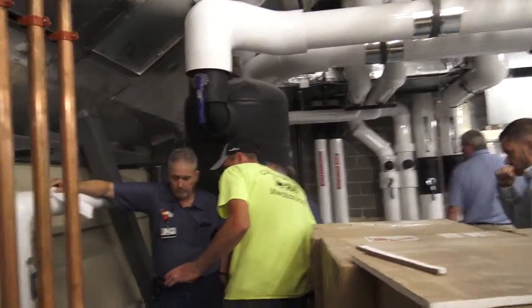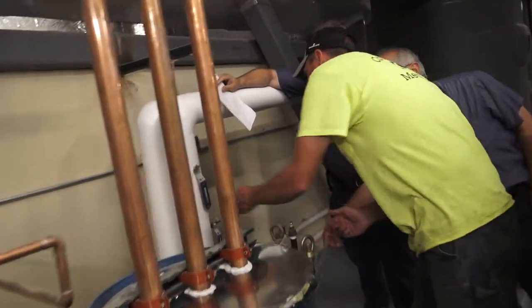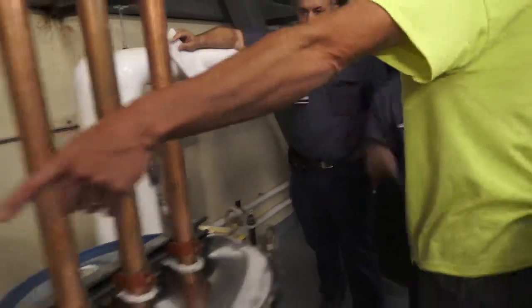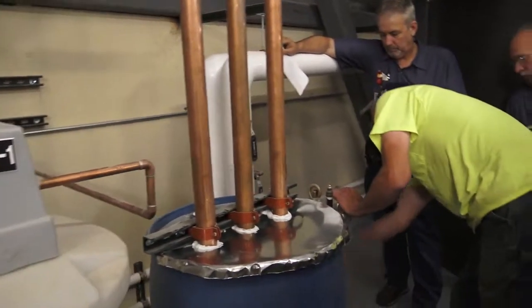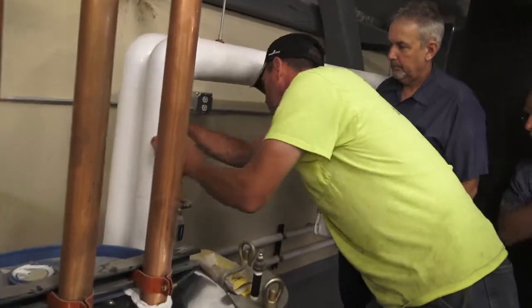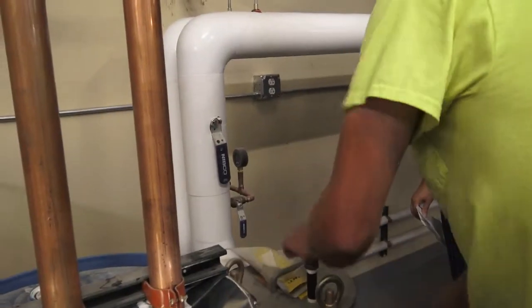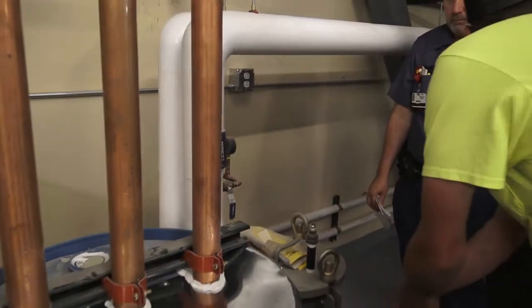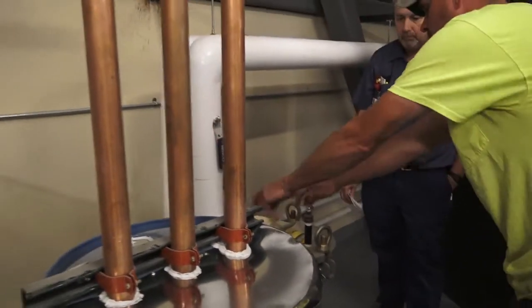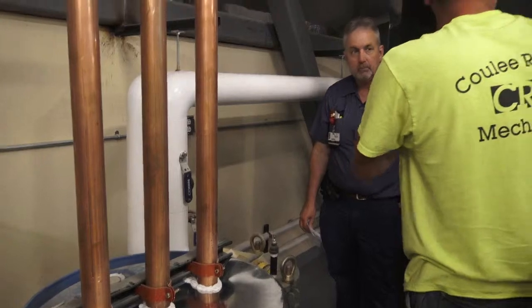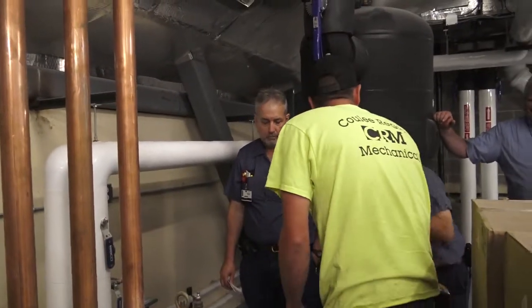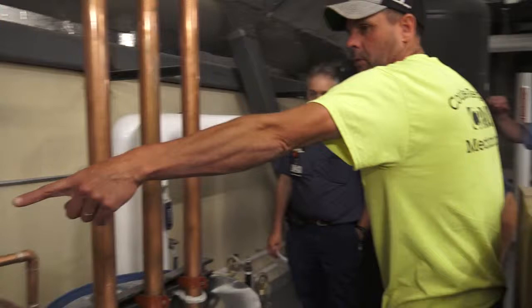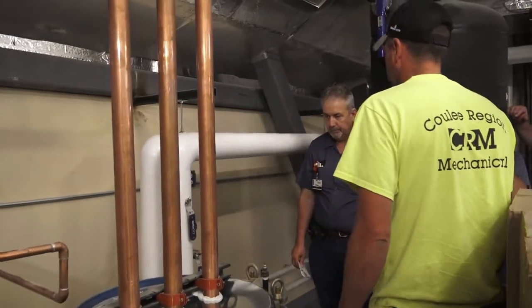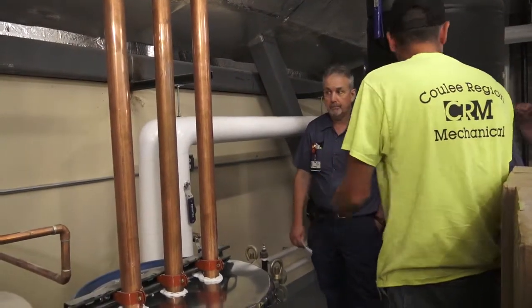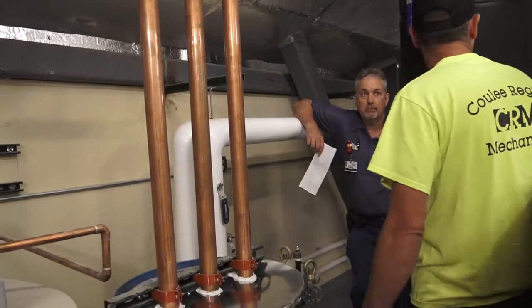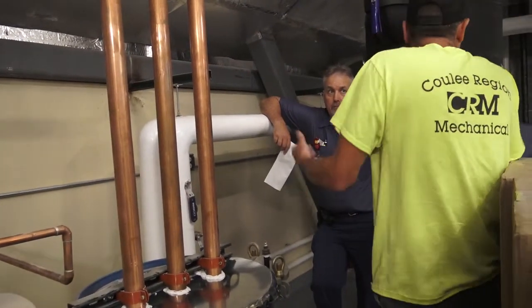But otherwise, the valves over here, once you shut this down, you bleed it off. That excess, do we just pour it back in? Yep, just undo that, take your hoses, shut where the valves are. There's a valve there, a bleeder, open it up, take a bucket and drop it in there. And you take that off and leave them off, they're just cartridges, that's all they are, shorter than the ones over here. Then just take that excess and dump it right back in there, and you're good to go. If you've got any problems with glycol, or if you reclaim it in a bucket, just take it right there and put it in so you save it.